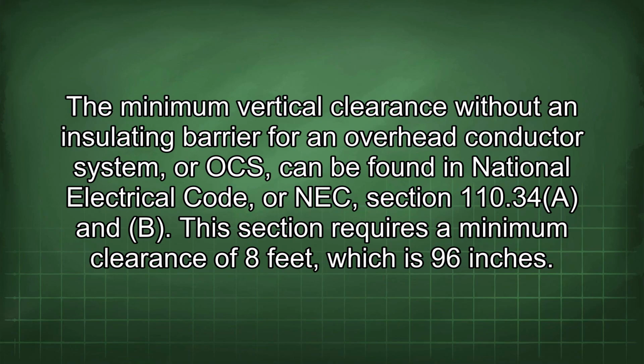The minimum vertical clearance without an insulating barrier for an overhead conductor system, or OCS, can be found in National Electrical Code, or NEC, section 110.34(A) and (B). This section requires a minimum clearance of 8 feet, which is 96 inches.